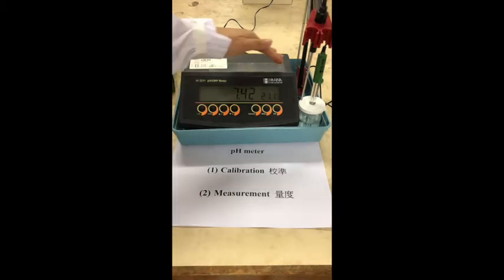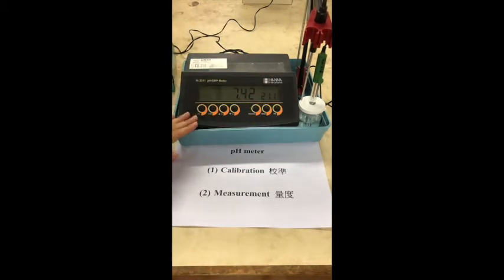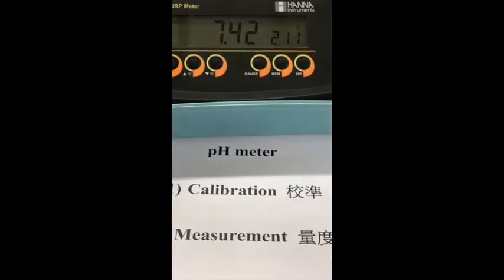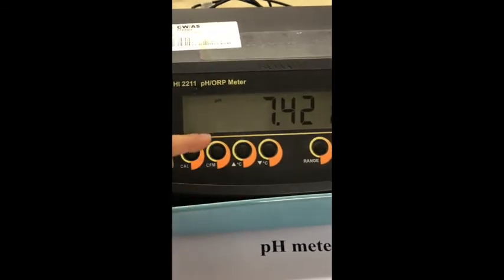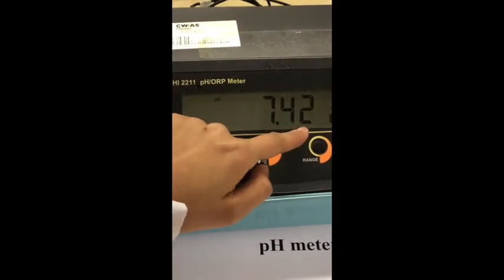Before the calibration, I would like to introduce the parts of the pH meter, the main control panels. This is the button for calibration. This is the confirm button, CFM. We need to press these two buttons during the calibration procedure according to the display. And this is the pH reading. You can see the pH, and now it's 7.42. And this pH is of the solution where the probe is placed.